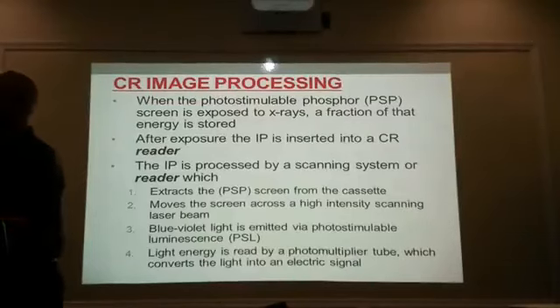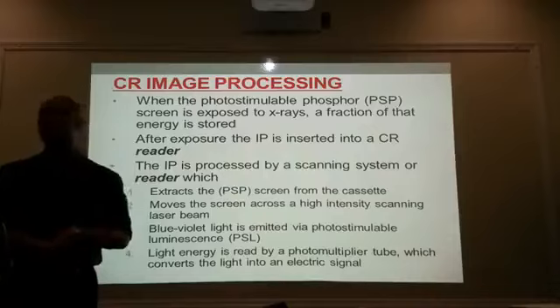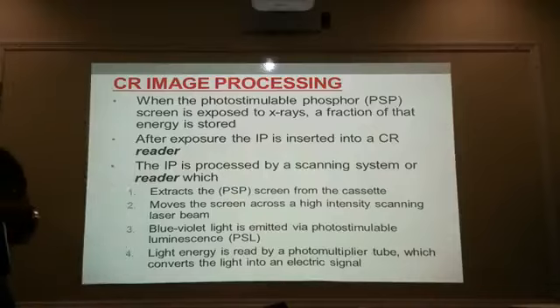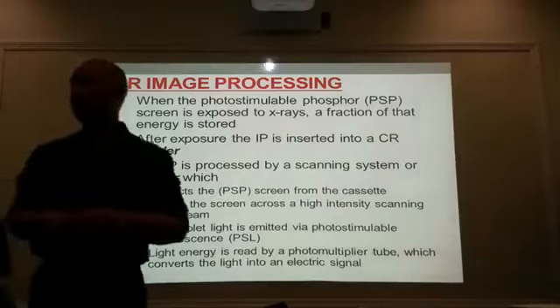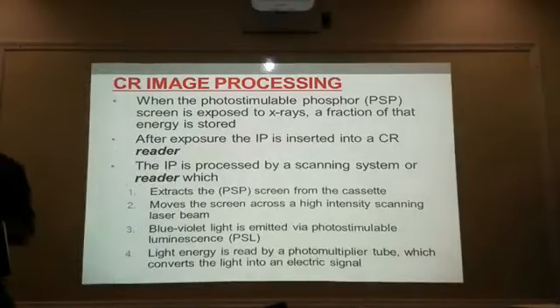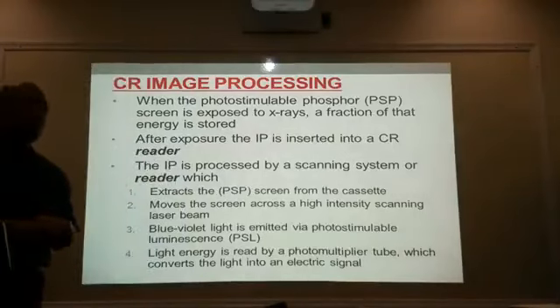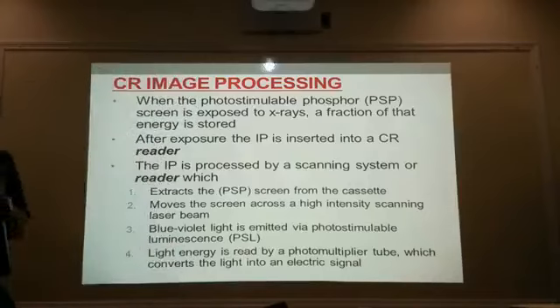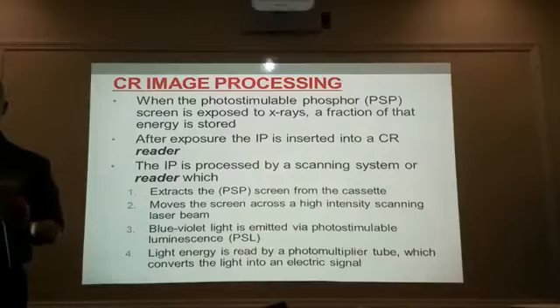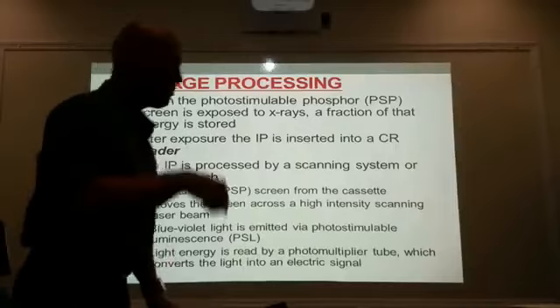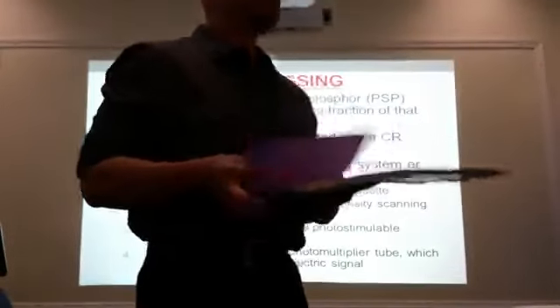When the photostimulable phosphor, the PSP screen, is exposed to x-rays, it's going to store some of that energy. After the exposure, the imaging plate will now be inserted into a reader to extract the image. With film, I have to go to the darkroom, open up my cassette, take my film out, and put it through the processor. With computerized radiography, it's all automatic.